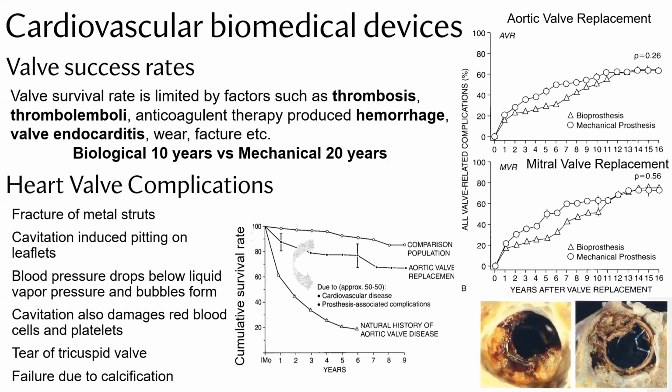So sometimes the reduced pressure in these circulation systems causes evaporation, and the bubbles that form then cause cavitation on these surfaces. And just like the cavitation that you see in a submarine, it's no different from that.